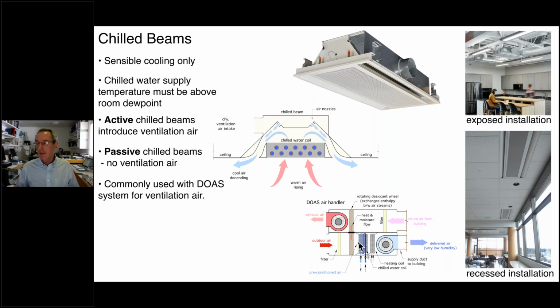We're trying to maintain, for example, 75-degree dry bulb, 50% relative humidity. We can use our psychrometric charts or software and figure out what the conditions of this airstream must be to achieve that desired air condition in the occupied space. Again, Hydronics 28 takes you through some of the calculations on doing that. So, a combination of a dedicated outside air system for ventilation and for latent cooling. And of course, our coil here is really going to be covered with condensation, because we're pulling lots of moisture out of that incoming airstream before we send it off to that occupied space.